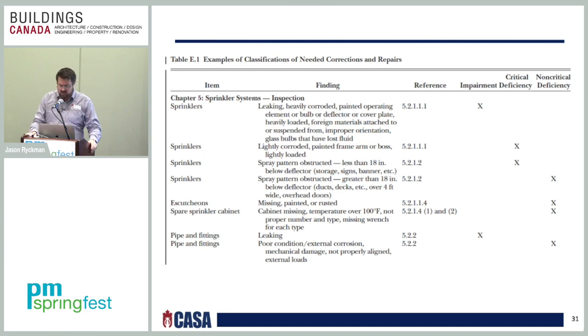Another thing that is interesting, that's in the Ontario Fire Code actually, in regards to obstructions, is 6.5.1.5. It stipulates that no obstruction shall be placed so as to interfere with the effectiveness of water discharge from the sprinkler. It also states that sprinkler systems shall not be used to support anything that will interfere with effective sprinkler system performance. So that's going outside the scope of NFPA 25, because in NFPA 25, remember, we assume that the design and installation is done correctly. And this ultimately becomes the fire code telling you that you have to do it. So it's very interesting. I just want to bring that up.